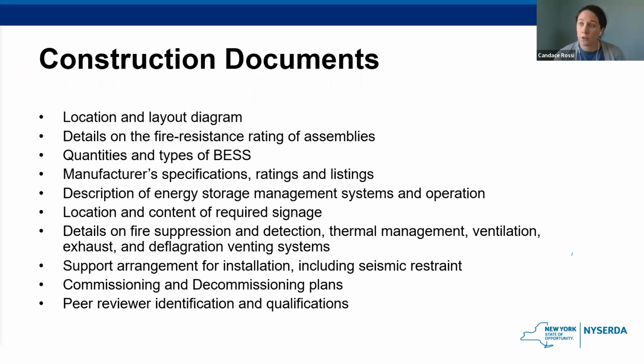So as part of the code, these are the construction documents that are required to be provided. So this is necessary along with the permit application. So we'll go through the code and go into more detail on many of these requirements and how they will be met. But as a minimum, they have to provide the location and layout diagram, details on the fire resistance ratings of assemblies, quantities and types of battery energy storage, the manufacturer specifications, ratings and listings, description of energy storage management systems and operation, location and content of required signage, details on the fire suppression and detection, thermal management, ventilation, exhaust and deflagration venting systems, support arrangements for installation, commissioning and decommissioning plans, and peer review identification and qualifications.